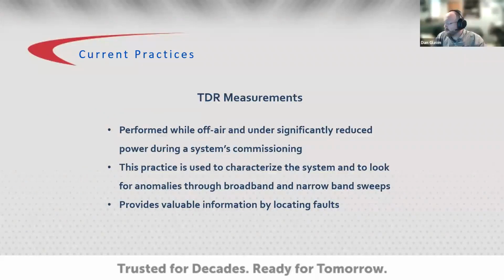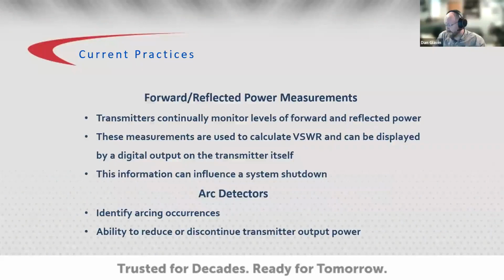So TDR measurements are performed while the system is off air, under reduced power or small signal analysis from a vector network analyzer during a system's commissioning. The measurement is used to create a benchmark for the initial system characterization and to find anomalies that may be present due to installation issues. The TDR provides valuable information by localizing faults in the presence of impedance mismatches.